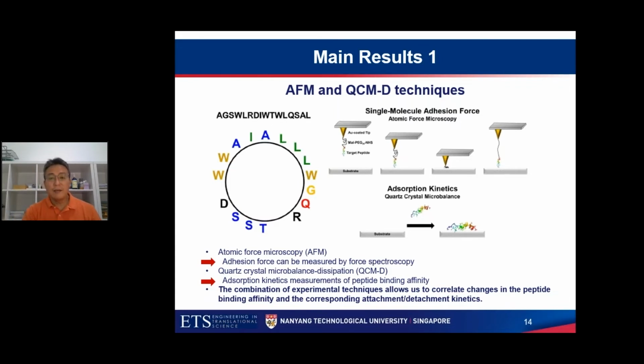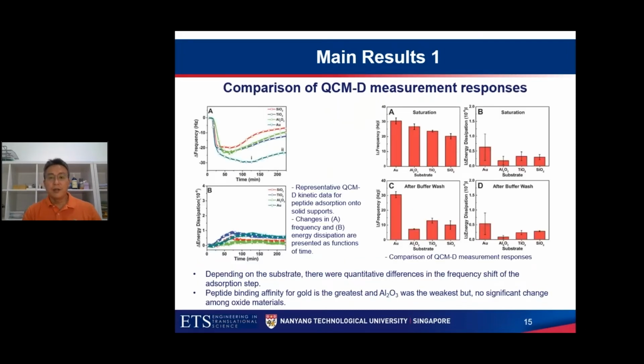And using AFM, one of the advantages is that you can actually measure the single detection. However, using QCM, quartz crystal microbalance, you basically measure the ensemble signal from the whole surface. That's the main difference. So by comparing with the QCMD data, you can actually see how the peptide interacts depending on the surface. And here it's showing silicon oxide, titanium oxide, gold, aluminum oxide, and so on. And then the frequency change basically corresponds to the mass adsorbed on the surface, which is the average event of a lot of molecules binding on the surface.